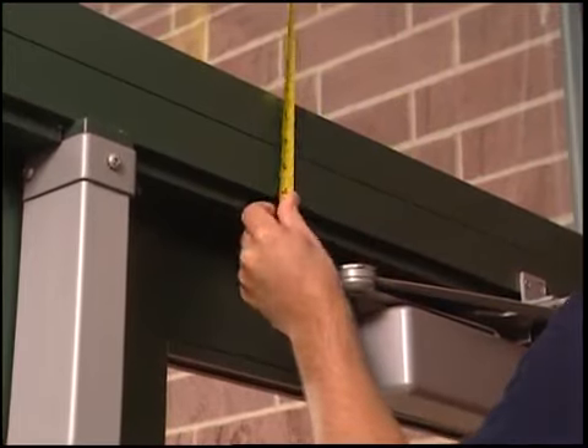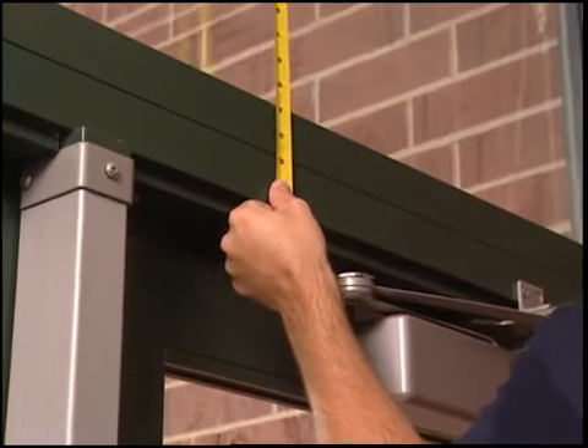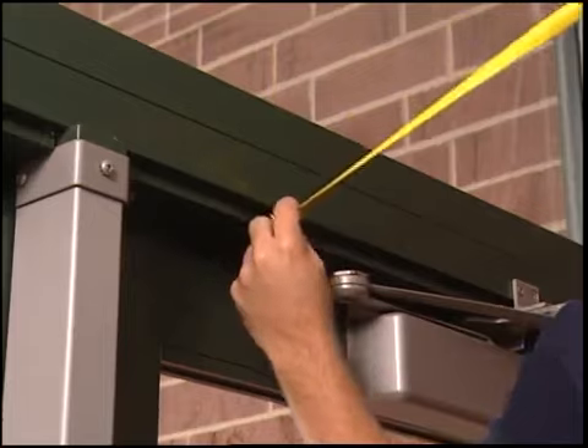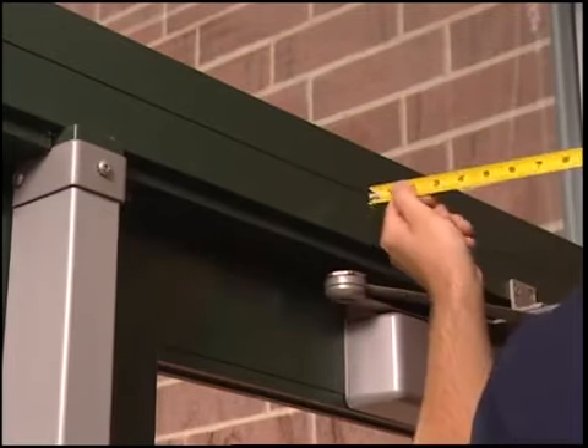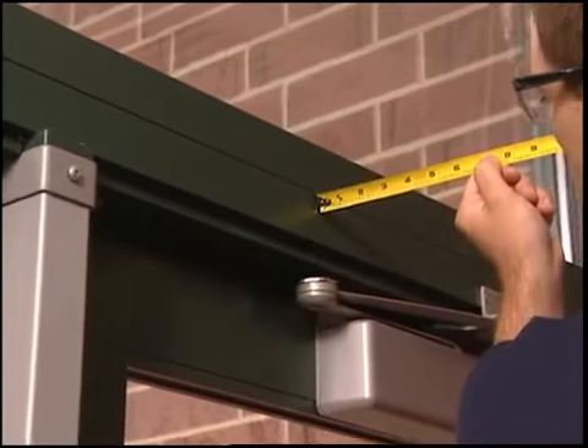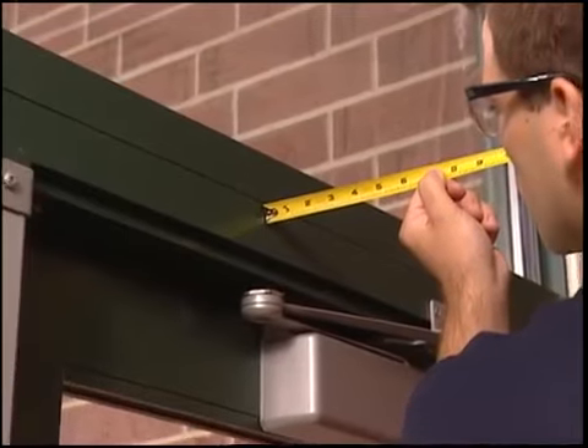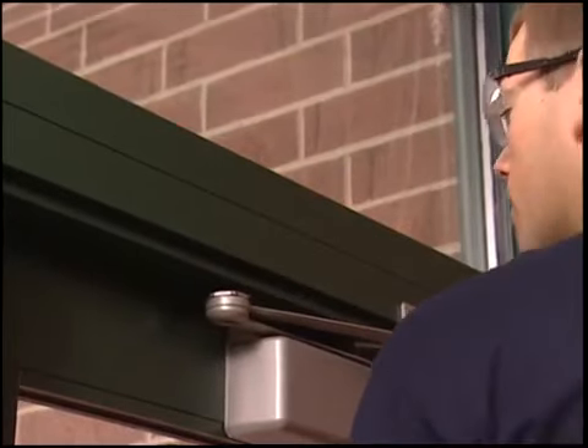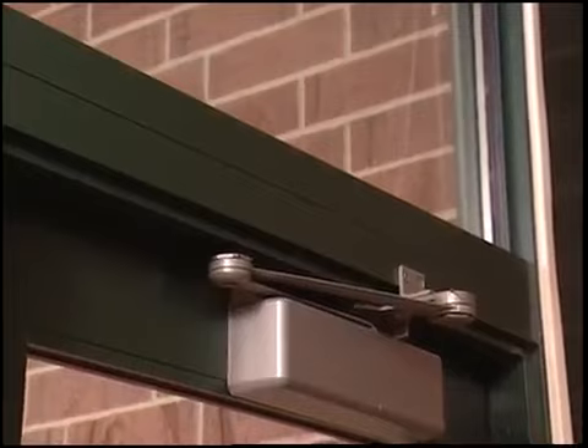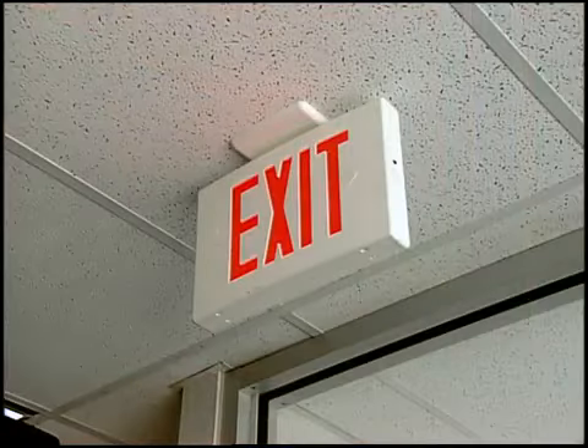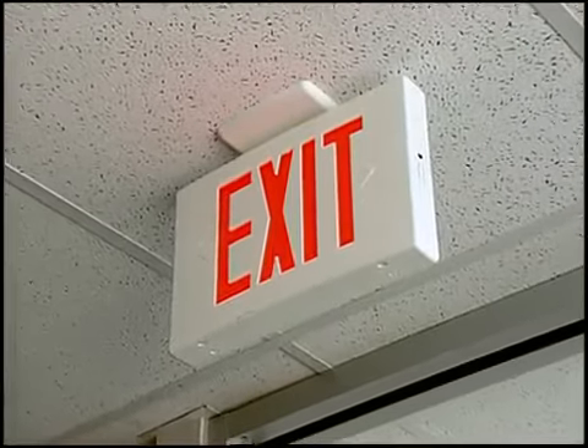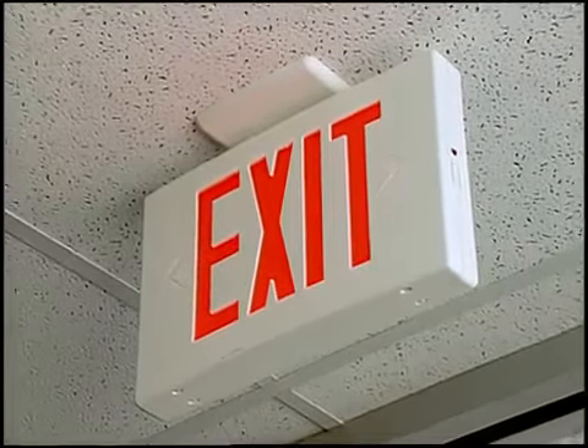Next, check the mounting channel clearances. You need a 4-inch clearance from the bottom edge of the frame. On the side of the door where the swing arm will be installed, you need a minimum 6-inch clearance, measuring from the face of the door frame out to allow enough room to install the unit and replace the cover. Check to verify that no obstacles, like an exit sign, will interfere with the operator.